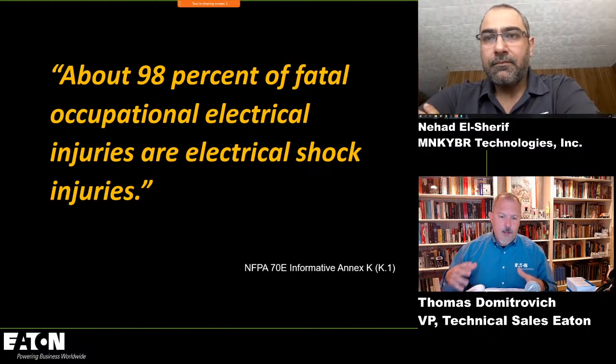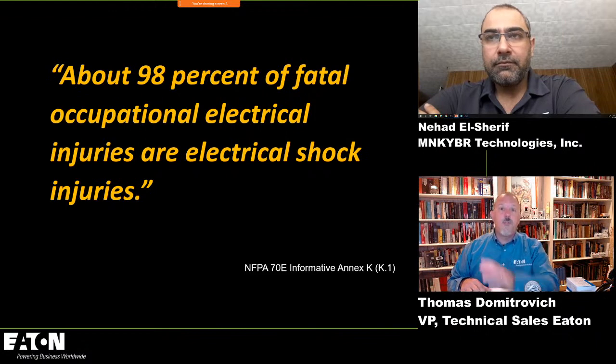in Annex K around shock, and a couple key things that I pulled out of that annex that I wanted to share on this call were some of the statistics. They say 98% of fatal occupational electrical injuries are electrical shock injuries. So, what strikes me, Nihad, is that when we talk safety, we love to talk about the explosions and the arc flash events, but a lot of people don't realize that more people die from shock every year than from things like arc flash events.